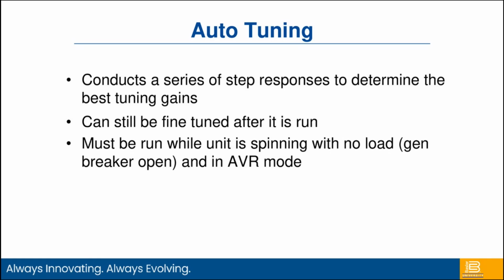While I'm doing this auto tuning function, the generator has to be running, and it needs to be spinning with no load. Of course, with the generator breaker open, and it has to be in AVR mode.